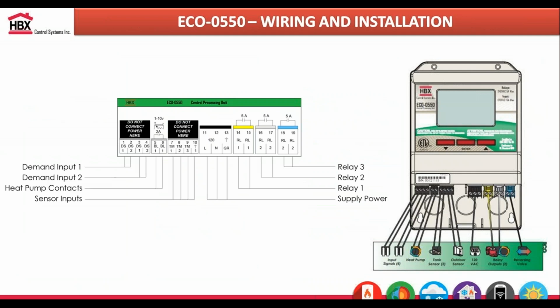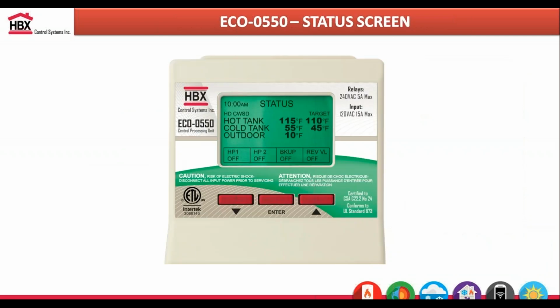In terms of the wiring, again, very straightforward. Everything is dry contacts, 240 at 5 amps, and he just uses those relays for the amount of heat pumps he wants to control. He can control that system pump, and then the last relay is to control the reversing valve. Again, log into those webinars later this month.